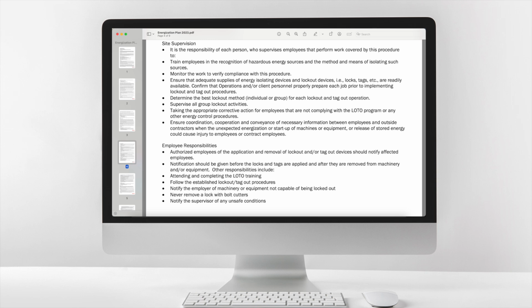Employee responsibilities. Authorized employees of the application and removal of lockout and/or tagout devices should notify affected employees. Notification should be given before the locks and tags are applied and after they are removed from machinery and/or equipment. Other responsibilities include attending and completing the LOTO training, following the established lockout, tagout procedures, notifying the employer of machinery or equipment not capable of being locked out, never removing a lock with bolt cutters, and notifying the supervisor of any unsafe conditions.